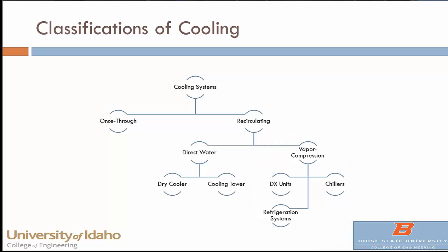Within the vapor compression cycle are DX units — direct expansion units — the typical things in your home refrigerator or home air conditioning, where the refrigerant carries the heat throughout the entire system. In industrial settings or large buildings, chillers are more common, where all the refrigerant stays in one unit and heat is transferred to a secondary working fluid, usually water or a water-glycol mixture. There are also high-end refrigeration systems using ammonia or increasingly carbon dioxide as the refrigerant, which can be multi-stage and much more complex.